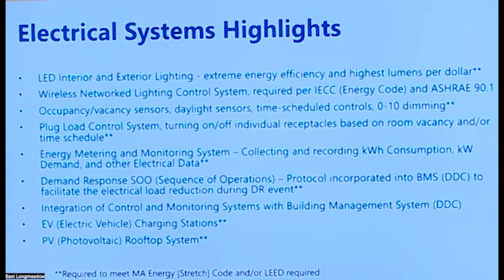What we're also implementing is what's called a demand response sequence of operations. It's a protocol that is incorporated into the building management system. What it does is facilitate electrical load reduction during demand response events. What it means is that either facilities or the utility companies, when they have this protocol in place, can request a temporary load consumption reduction and other energy saving measures. And all these control and monitoring systems are integrated with the building management system. We call it the DDC system. What we're also implementing into the design is obviously electric vehicle charging stations. We'll get into that too. And a photovoltaic rooftop system. Next page, please.